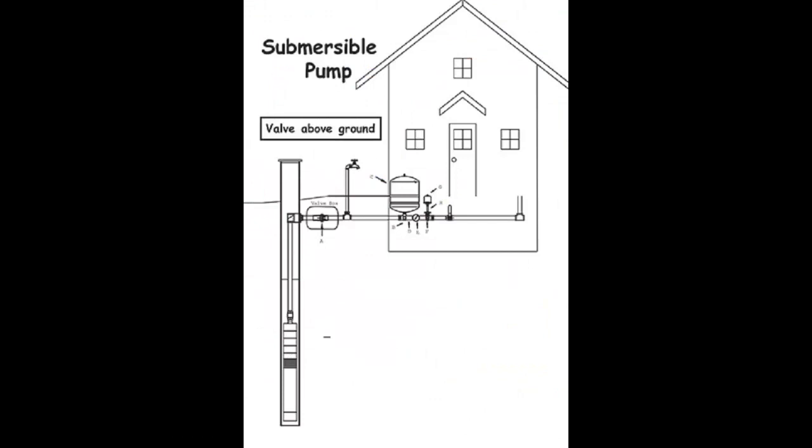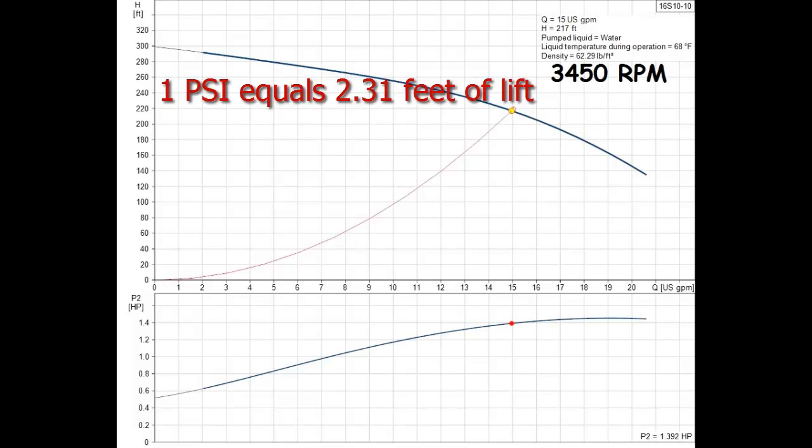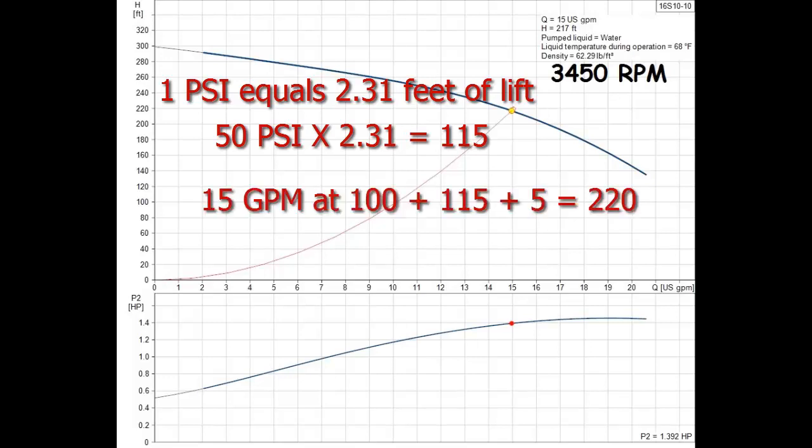Another example is a residential application which has a required demand of up to 15 gallons per minute at 50 psi and needs to lift from a well with a pumping depth of 100 feet. To a pump, one pound of pressure is the same as 2.31 feet of lift. So to get 50 psi at the faucets the pump must produce 50 times 2.31 or 115 feet of lift.